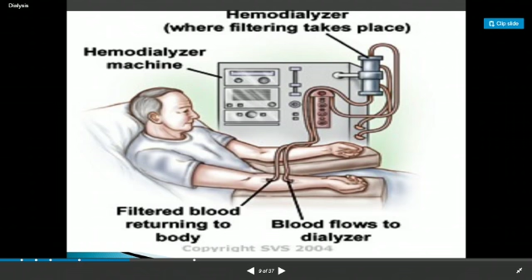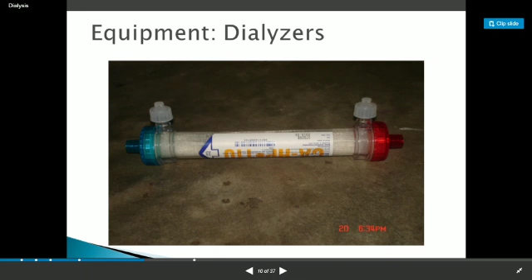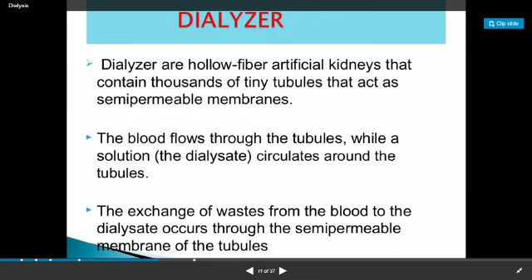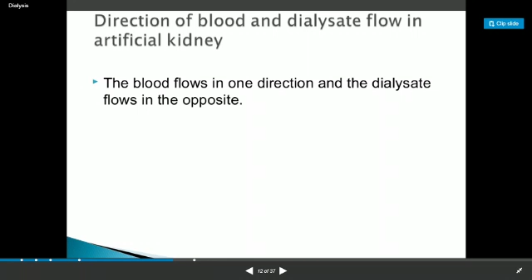Here you're watching the main equipment which is known as the dialyzer for the hemodialysis process. In this dialyzer, which is acting as an artificial kidney, a fluid is used which is known as the dialysate. So dialyzers are the hollow fiber artificial kidney that contain thousands of tiny tubules that act as semi-permeable membrane. The blood flows through the tubules while a solution called the dialysate circulates around the tubules. The exchange of wastes from the blood to the dialysate occurs through the semi-permeable membrane of the tubules. Direction of blood and the dialysate flow in the artificial kidney: the blood flows in one direction and the dialysate flows in the opposite. So this figure is representing how the blood and the dialysate are moving in the opposite direction.